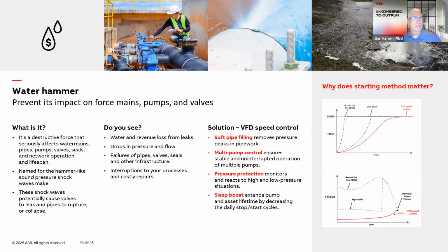So there's a couple problems that we'll discuss next that are found in water treatment systems that cause downtime, and we'll talk about how to avoid them by applying variable speed drives. Those two issues are water hammer and pump cavitation. Water hammer is caused by the rapid acceleration or deceleration of fluid in a pipe. So starting a pump with maximum torque without a VFD will cause that pump or motor combination to rapidly accelerate and cause the water in the pipe to slam into the valves, the pipe joints, and rapidly pressurize the pipe run.